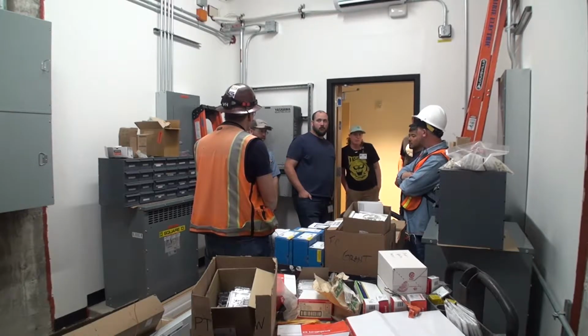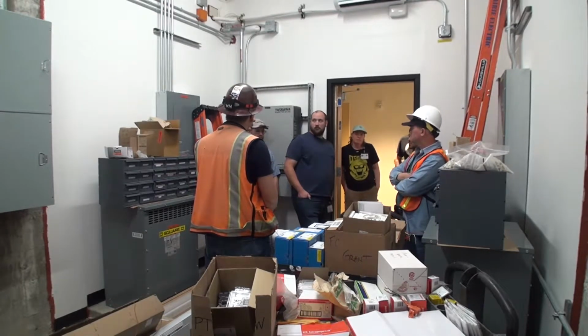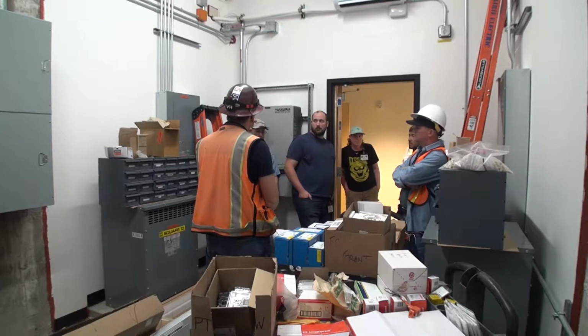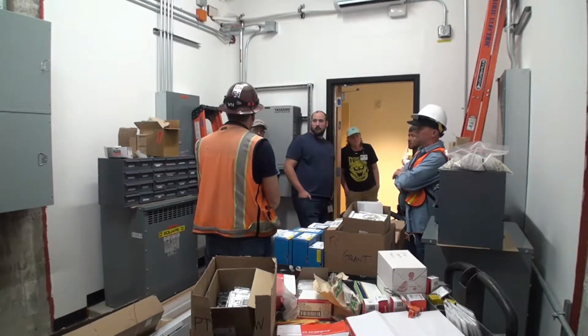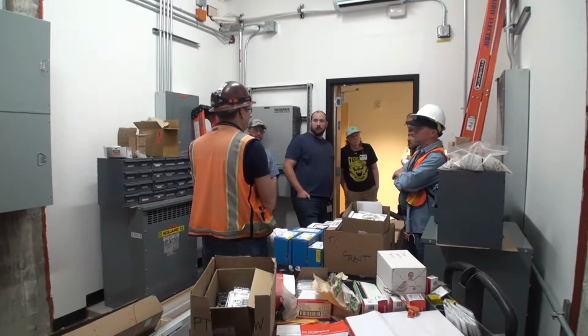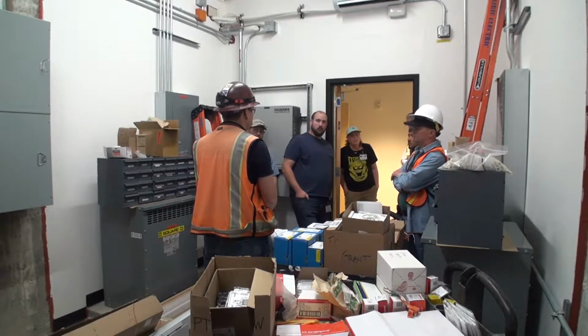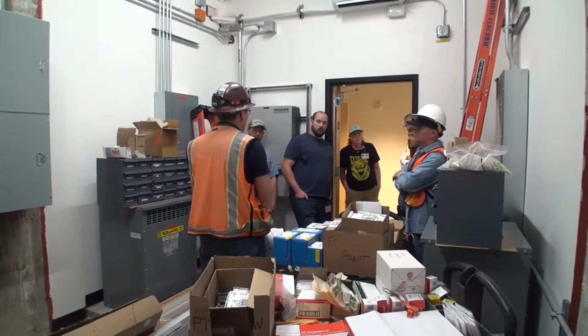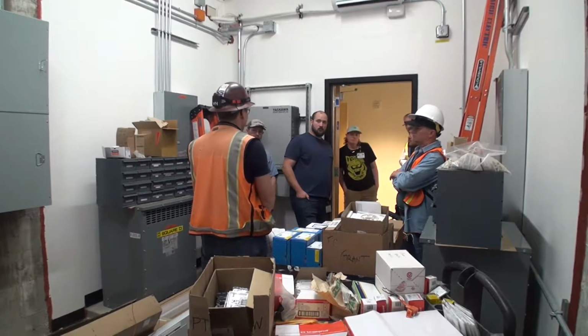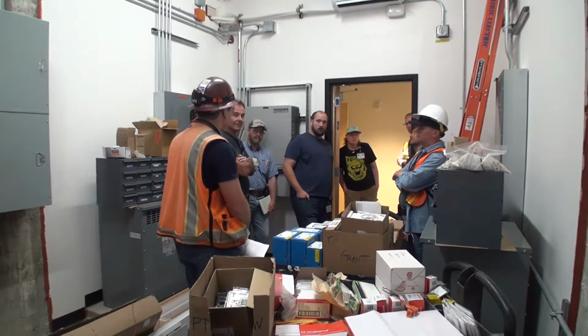Call it standby instead of emergency. Standby is a step lower than emergency. Standby would be like you want a refrigerator to not defrost. The biggest thing with emergency is the emergency lighting, your egress path.